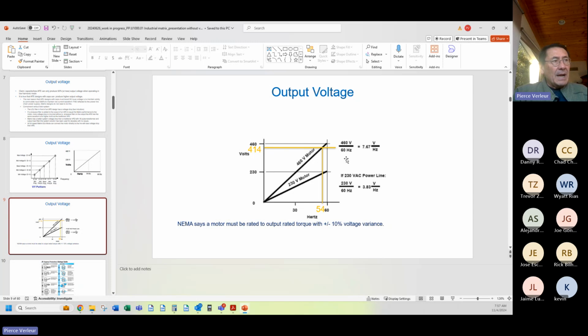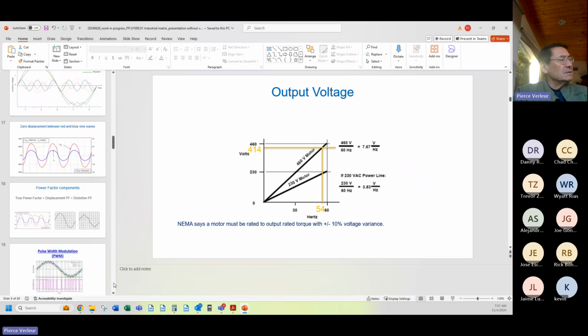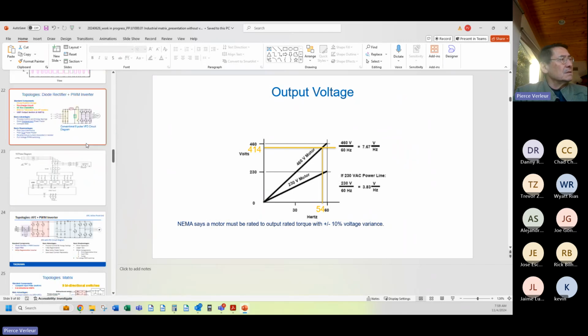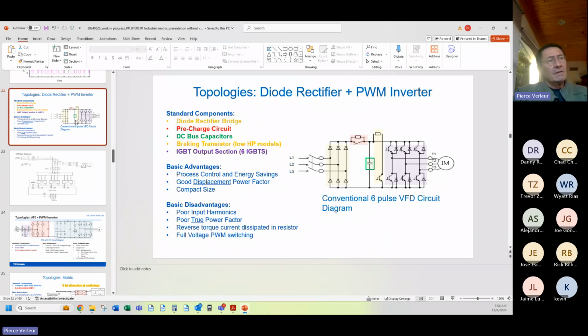Now, most power in the United States is 480 volts versus 460 volts, so that helps us a little bit. And the matrix drive voltage drop is not 10%. But if we compared this to the other topologies, we have to ask ourselves, what's the voltage drop across this drive? It's not zero. And look at the number of components we're going through with matrix technology.